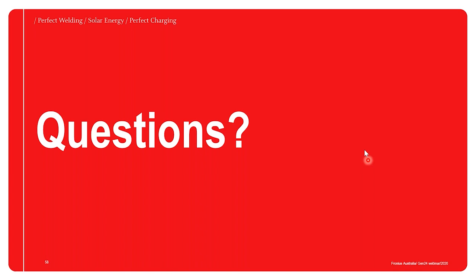Would you recommend putting the total array across one MPPT or spreading it across two? It really depends on what you have there. What I usually do: if I need 2 trackers, then yes, but if I only need 1 tracker, it depends if you want to go all in one direction or have multiple orientations. For most residential houses, 2 trackers is good so you can get the most out of it, but it really depends. And if I can go above 600 volts, that's basically my option, or what I would select. I'd prefer to have longer strings in general.